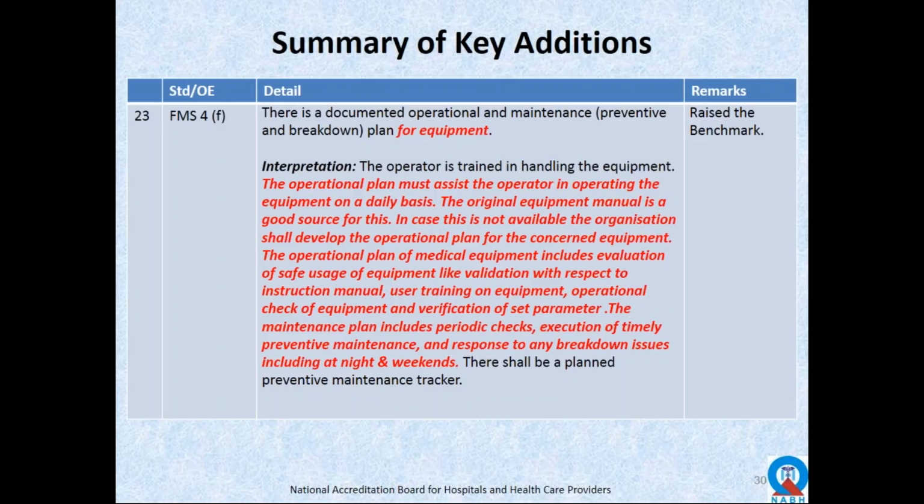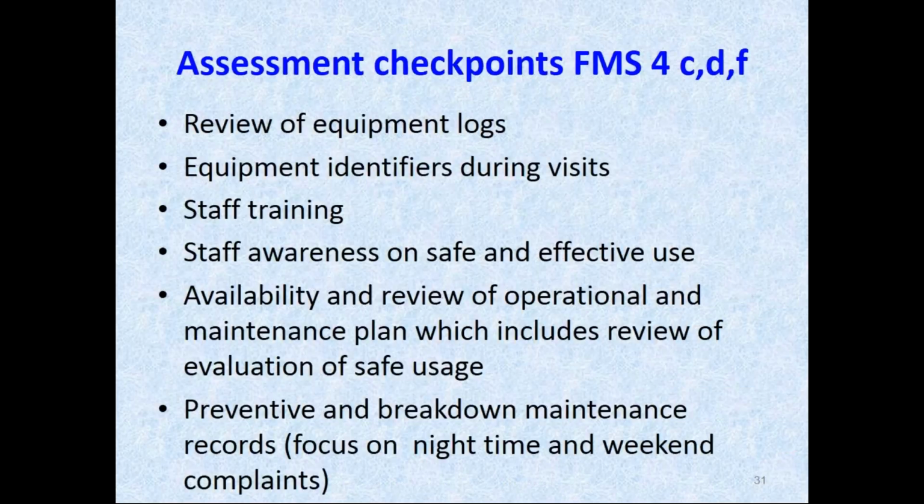Assessment checkpoints for the medical equipment maintenance, where we would look at the review of equipment logs, whether the log shows unique identifiers. During visits also we can check whether each medical equipment has been identified uniquely and given a unique identifier code. Staff training on the use of equipment, staff awareness on the safe and effective use also can be checked by staff interviews.